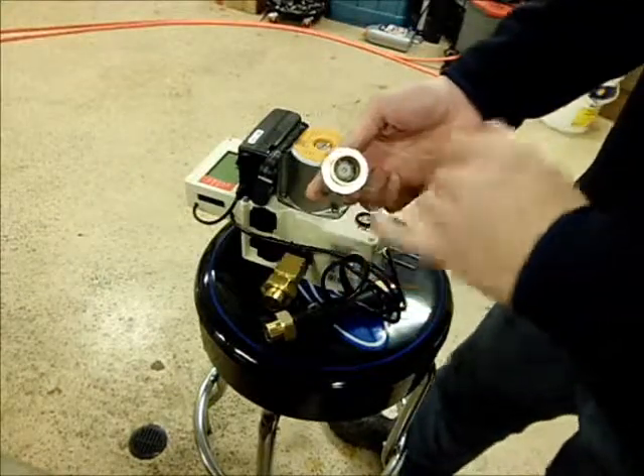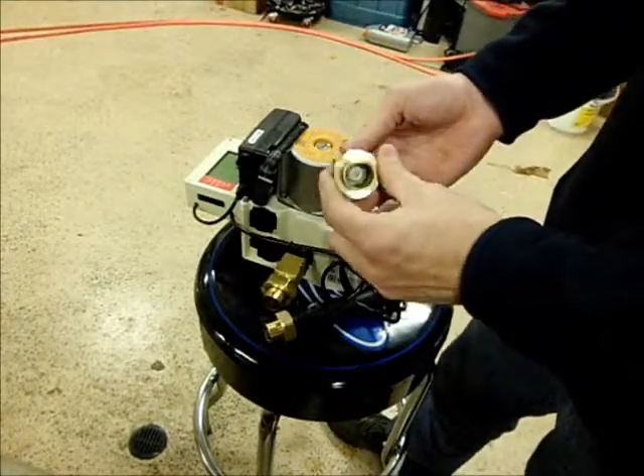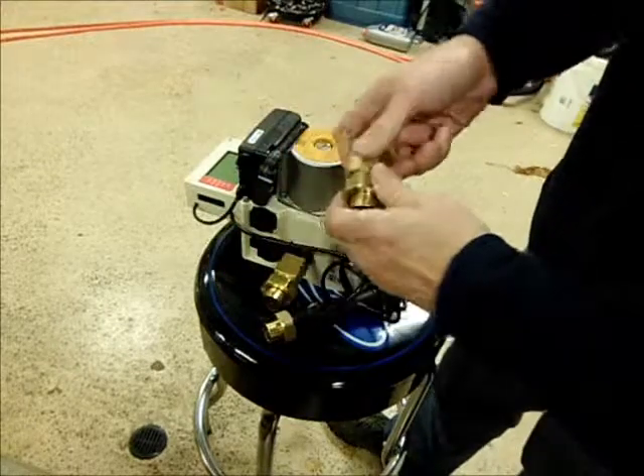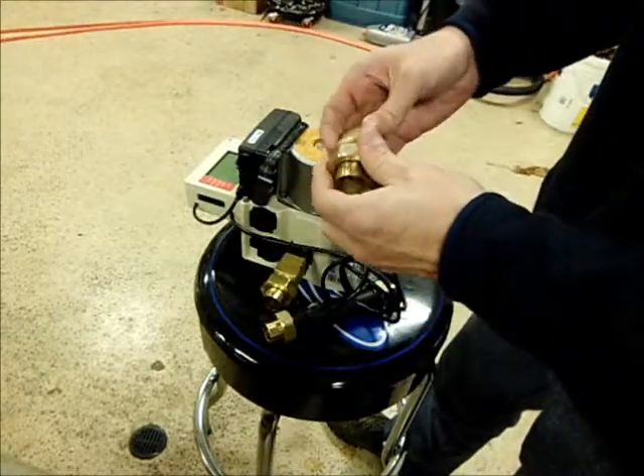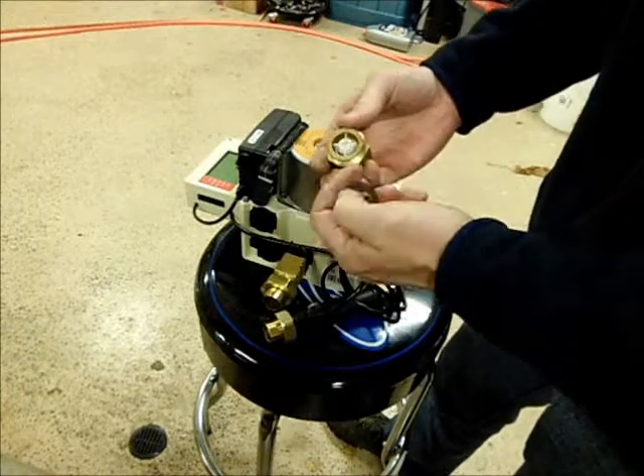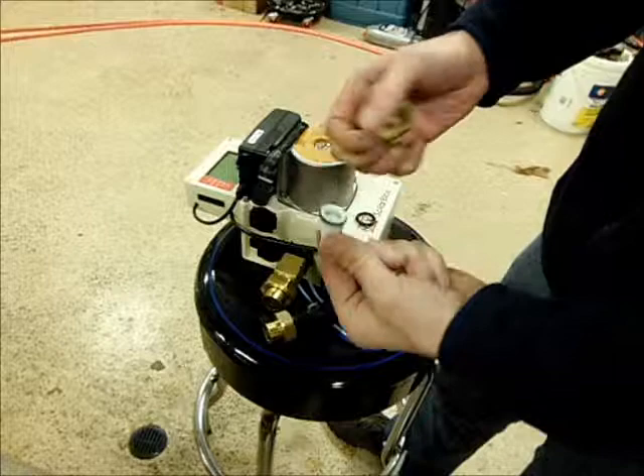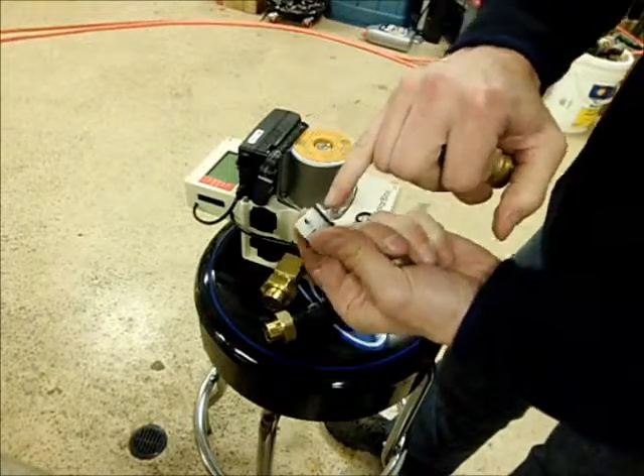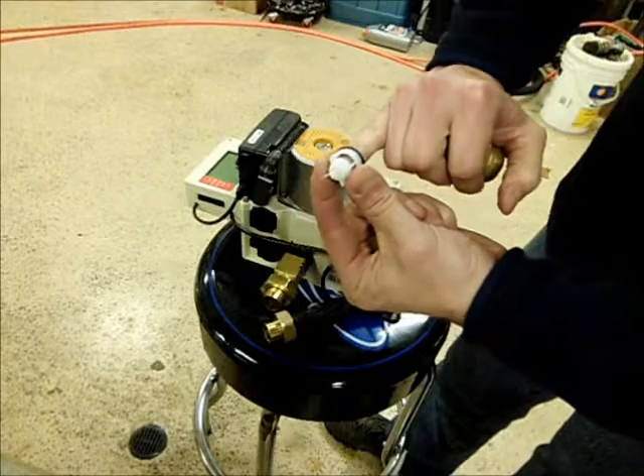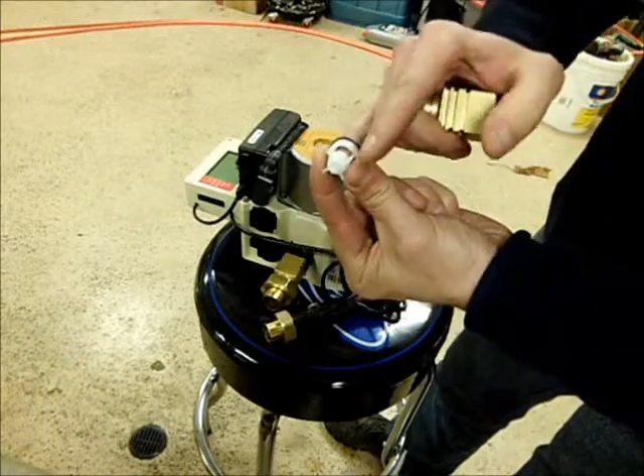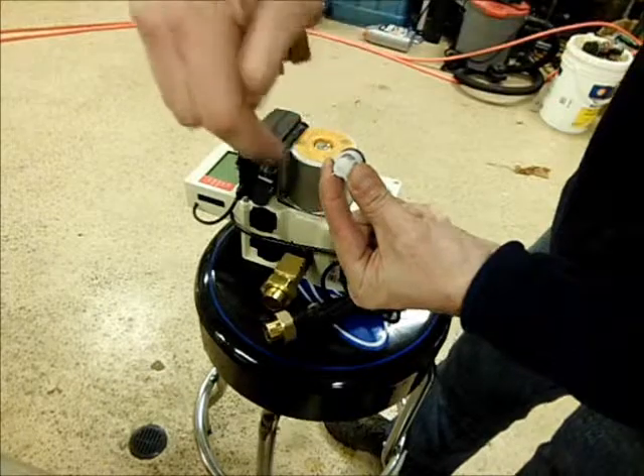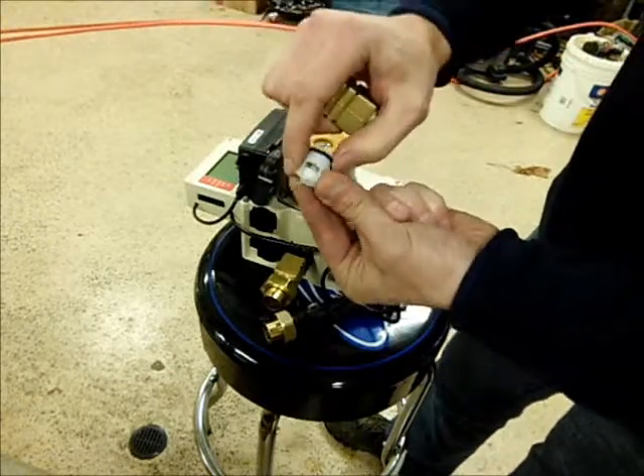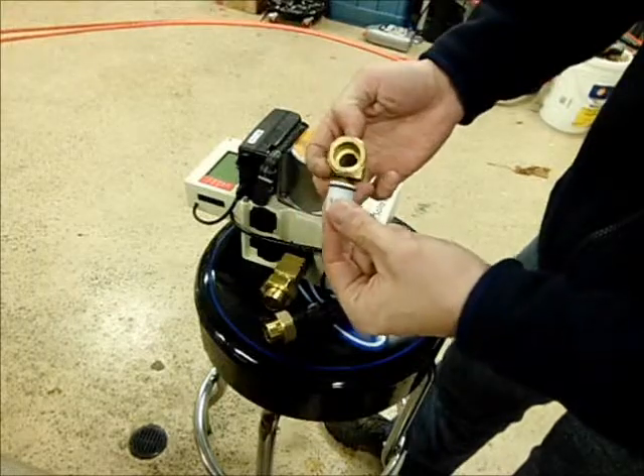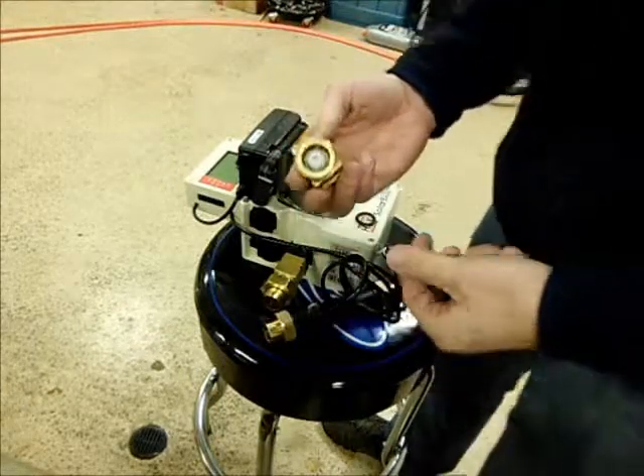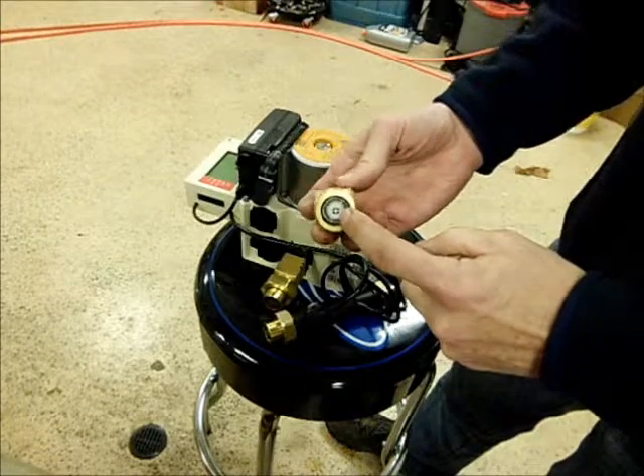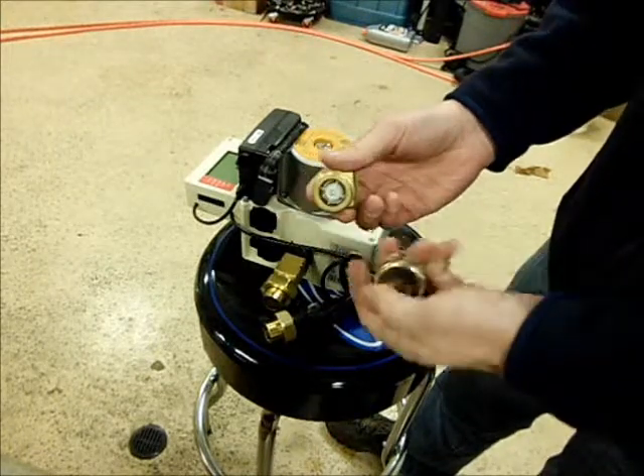Okay, this is the output fitting. It has a one-way valve in there to prevent thermosiphon. The flow goes through this way. If we pull this apart, you can see the little valve on the inside. The way it works is that little ball on the inside there gets pushed forward by the fluid flow. As it's pushed forward, you can see the fluid come through and go in that direction. If it tries to thermosiphon in a reverse direction, there's a tiny spring in there and it just seals that up tight, so there's no flow in the reverse direction. So make sure that that valve is oriented correctly in your output fitting.